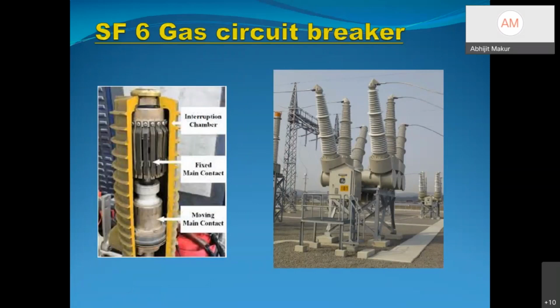SF6 circuit breakers and vacuum circuit breakers are the two that are presently in service at most utilities and consumer levels. But SF6 gas, being a greenhouse gas, as other panelists have discussed, is supposed to be phased out, and some international regulations will come in due course, as it harms the environment. However, vacuum circuit breakers up to 132 kV are in service, and the maintenance cost is very low. So this is the preferred form of circuit breaker in most of the utilities and consumers.